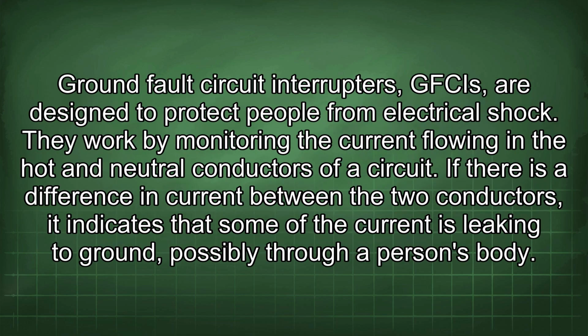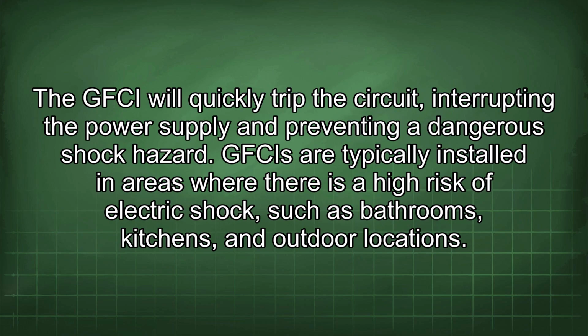Ground fault circuit interrupters, GFCIs, are designed to protect people from electrical shock. They work by monitoring the current flowing in the hot and neutral conductors of a circuit. If there is a difference in current between the two conductors, it indicates that some of the current is leaking to ground, possibly through a person's body. The GFCI will quickly trip the circuit, interrupting the power supply and preventing a dangerous shock hazard. GFCIs are typically installed in areas where there is a high risk of electric shock, such as bathrooms, kitchens, and outdoor locations.